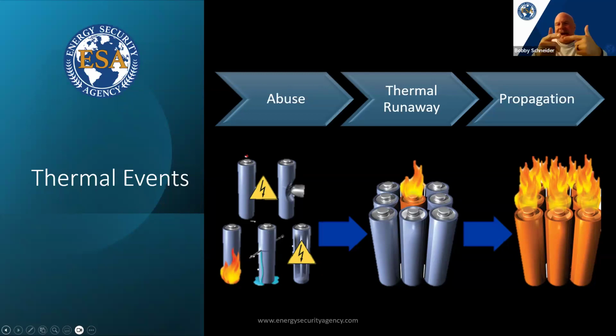That can create off-gassing. A lot of these cells have microvents in them in the design of them. So then as the off-gassing builds up and pressure builds up, it may be a slower release, and it will start releasing that off-gassing that may become visible. I may visibly see it, I may smell it, I may pick it up with a 4-gas meter or my thermal imaging camera - I'll jump into that here in a little bit. But that is what we call a thermal event.